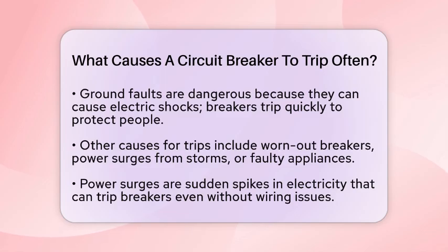Other reasons for frequent trips include worn-out breakers that no longer work properly, power surges from storms or lightning, or faulty appliances that draw too much current. Sometimes a breaker trips because it's old and needs replacing. Power surges cause sudden spikes in electricity, which can trip the breaker even if your wiring is fine. Faulty appliances with internal wiring issues can also cause trips.